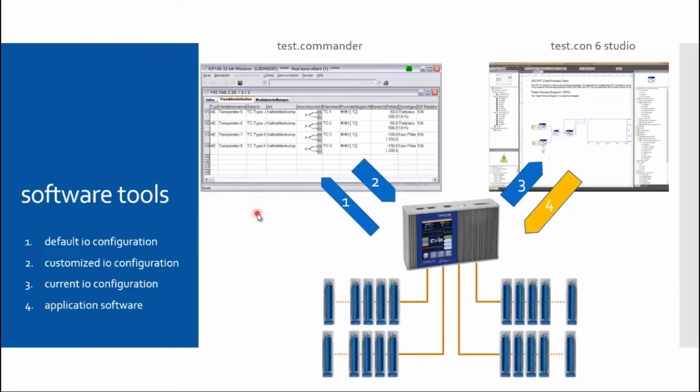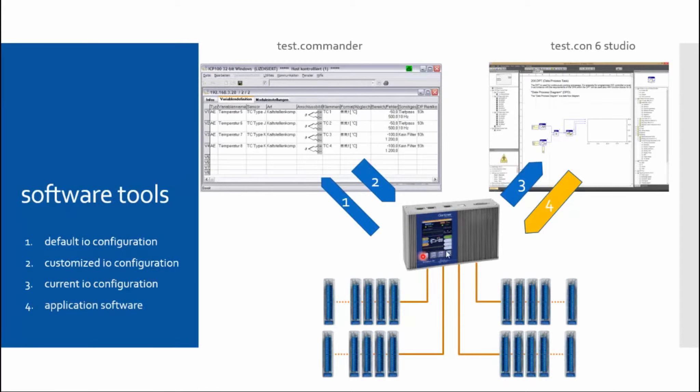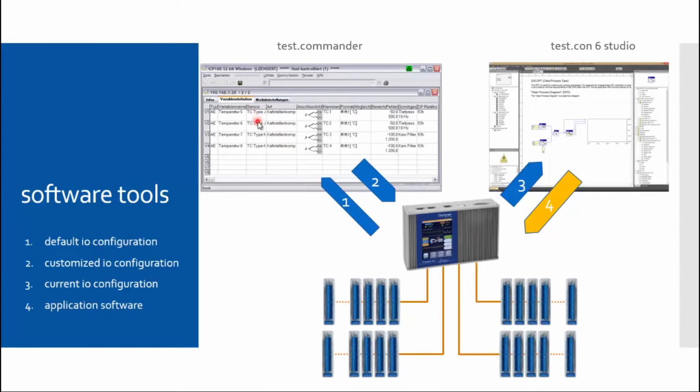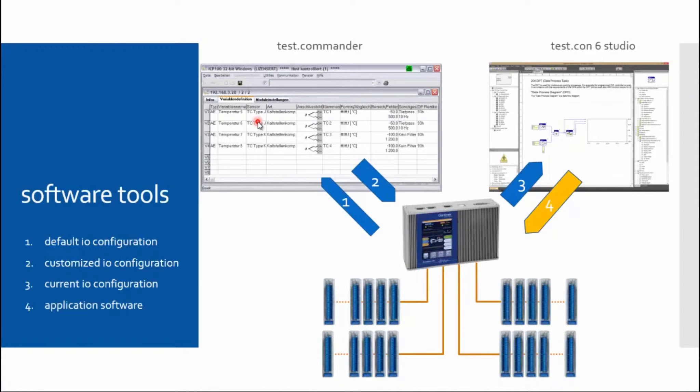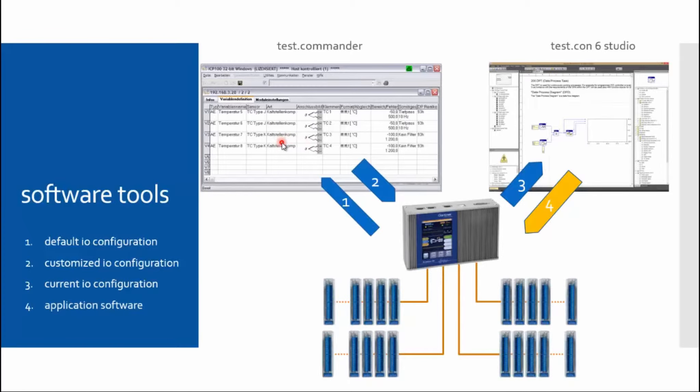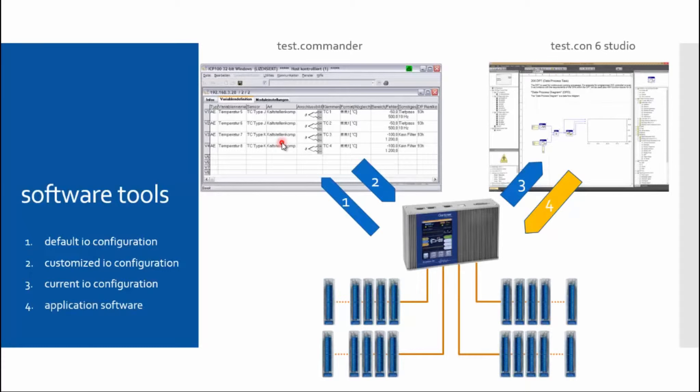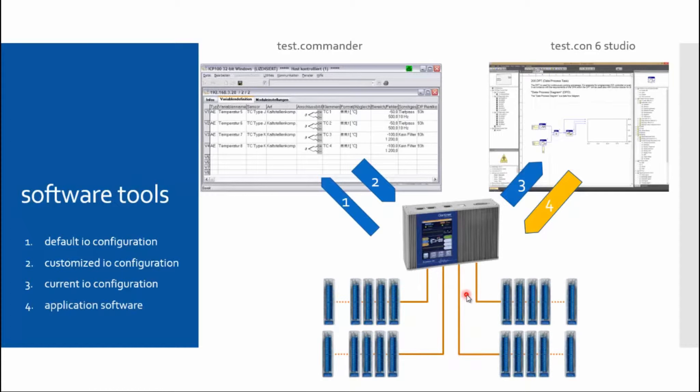At first, I am scanning the target device, which is the Q.station here. I read the standard configuration which the system has scanned itself. It recognizes the connected modules. On basis of the default configuration, I can adapt my own configuration to my needs. For example, I can designate an I/O as a current channel or I can designate an input to be a voltage channel. Or if I want to work with the 4 to 20 ampere at some point, that is possible to configure. And you can also assign variable names, etc. You probably know that if you have already worked with TestCommander. When the configuration is done and cycle time is implemented, the configuration has to be downloaded on the Q.station.